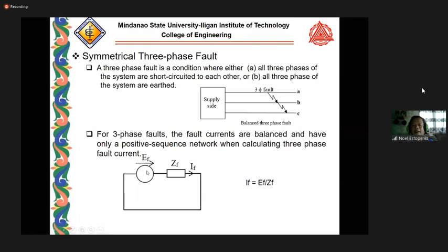For the analysis of the three-phase fault, the fault currents are balanced since it is symmetric. This means we will only consider the positive sequence network when calculating the three-phase fault current. So in the equivalent circuit, we just short the voltage which is in series with the fault impedance. What we will get when we solve for the fault current is the pre-fault voltage over the fault impedance.